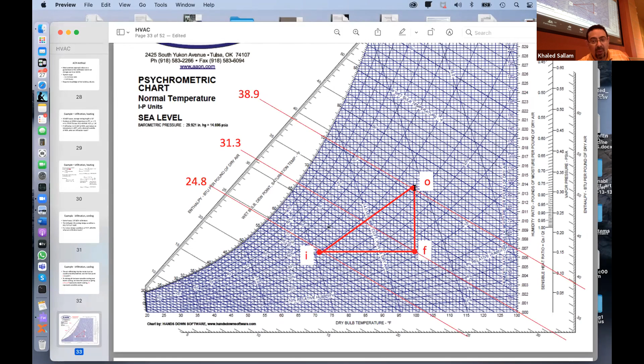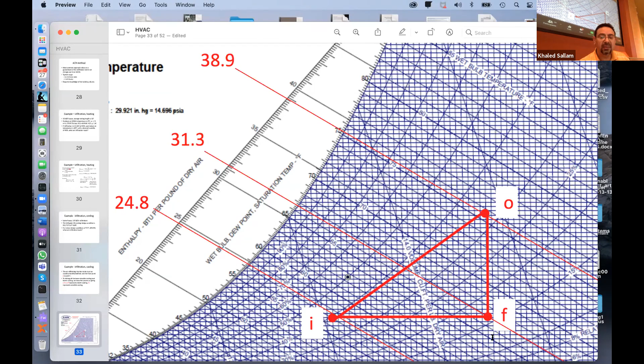So 38 minus 31, that is... how much is that? That is the latent heat. And the 31 minus the 24, that is the sensible heat. Okay, so if you want to cool that outside air back to this, you have to pay for this and this: this many BTU per pound of dry air and this BTU per pound of dry air.